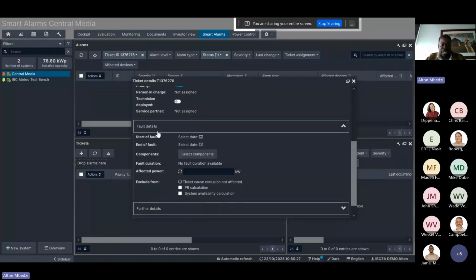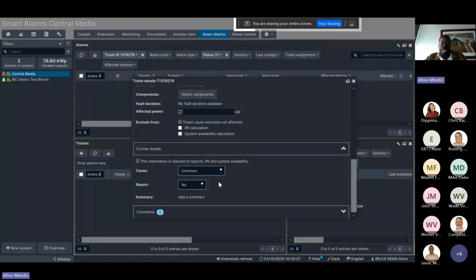Then you can set the fault date, start date, and which components were affected — was it a breaker? You select the component and how much affected power there was. Do you want to exclude this from the performance ratio calculation? Because when the site goes down, the performance ratio goes down. If you want to exclude it for some reason — maybe it was operation and maintenance — you don't want it counted, so you can just select exclude. Then you can add more details: report yes or no, summary, comments — you can add comments every day.